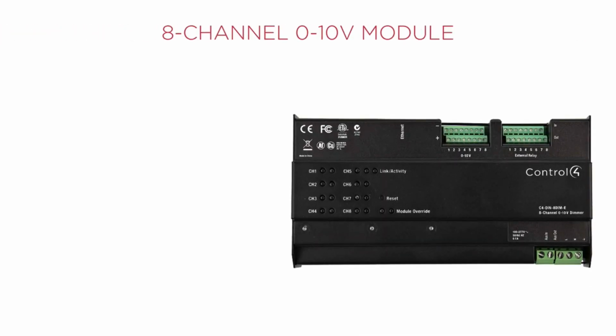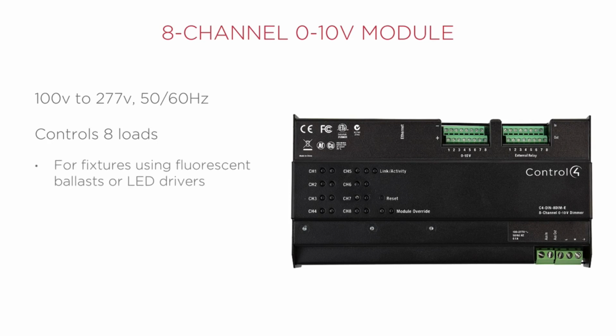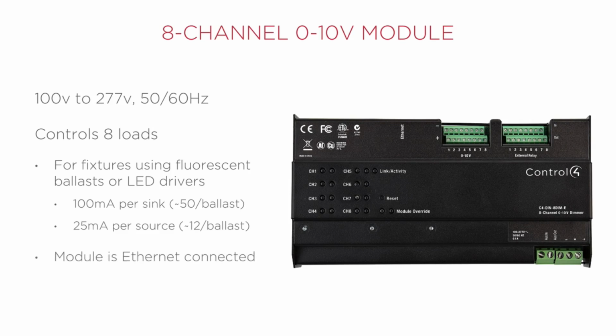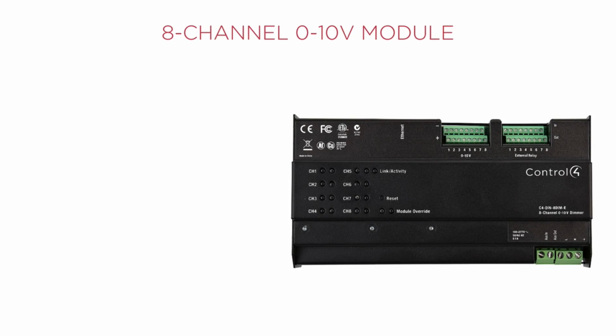The 8-channel 0 to 10 volt dimmer module works from 100 to 277 volts at 50 or 60 Hz and controls 8 loads. It can be used for fixtures using fluorescent ballasts or LED drivers. It can provide 100 milliamps per sink, which is approximately 50 per ballast, or 25 milliamps per source, which is approximately 12 per ballast. The module is Ethernet connected, and those loads are controlled by keypads.